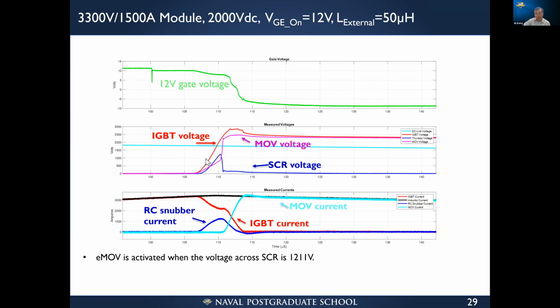Right? As you can see, around here the IGBT started to turn off. The IGBT current will start to decrease, and at this time the MOV has not been kicking in. So most of the current will flow through the snubber, but the voltage across the IGBT will start to increase. Right? This is the green curve starting to increase. And these voltages will be shared by the MOV and SCR. Once the SCR voltage increases to a certain point, around 1200 volts, we take the breakover diode voltage rating at around 1200 volts. The breakover diode will turn on.